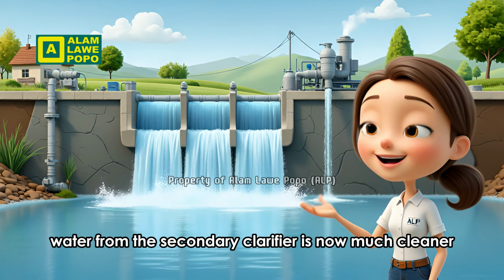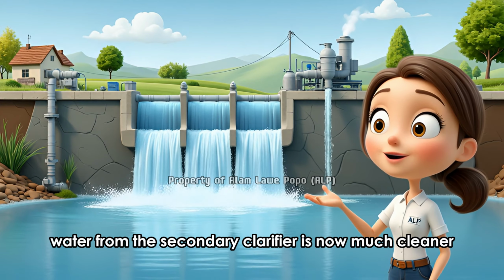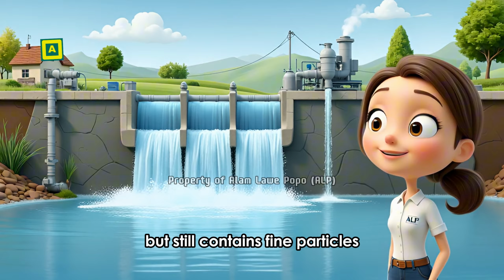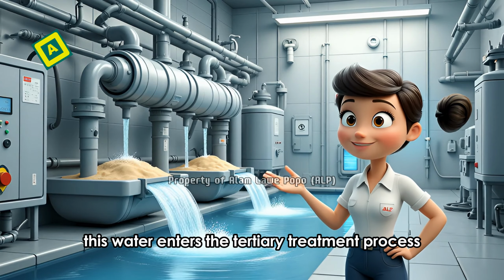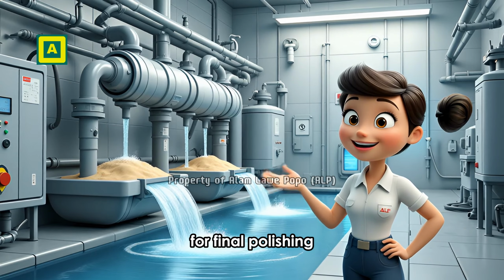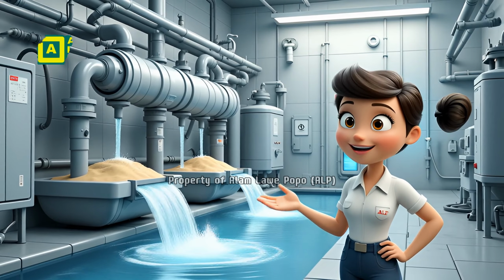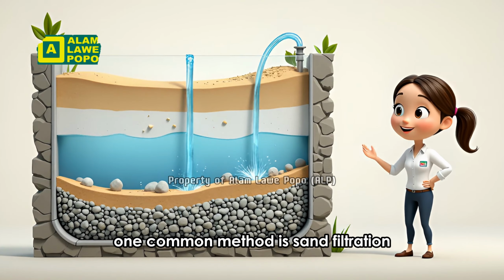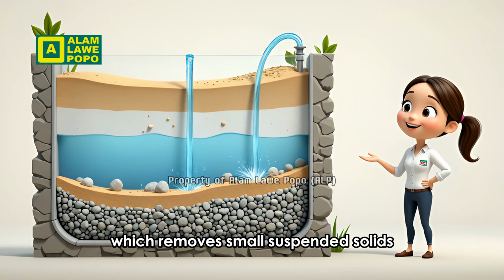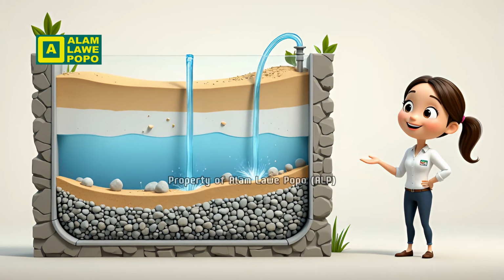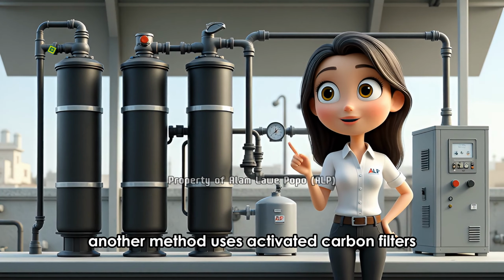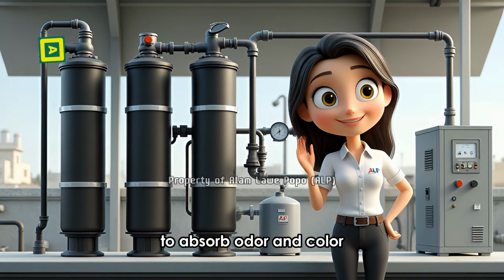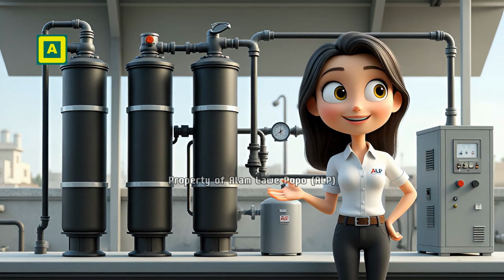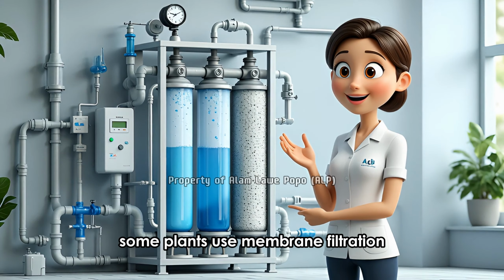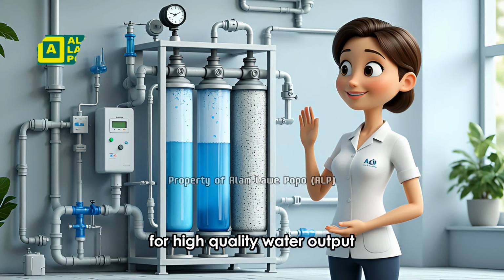The clear water from the secondary clarifier is now much cleaner, but still contains fine particles. This water enters the tertiary treatment process for final polishing. One common method is sand filtration, which removes small suspended solids. Another method uses activated carbon filters to absorb odor and color. Some plants use membrane filtration for high-quality water output.